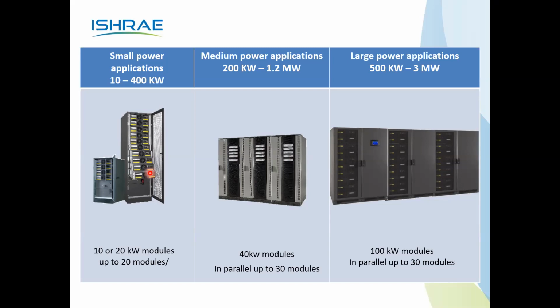But with a true modular UPS, it is possible to upgrade the UPS capacity without any shutdown, as well as to fix problems. If any module has a problem, to fix it, no need to shut down the load, no need to shut down the UPS systems, and no need to transfer the load to the bypass. Without doing that, online, that faulty module can be swapped. That is the main purpose for going for modular: scalability, serviceability, and easy maintenance. Here in the picture, you can see there are various ratings available. It starts from 10 kilowatt, 20 kilowatt, 40 kilowatt and 100 kilowatt modules.